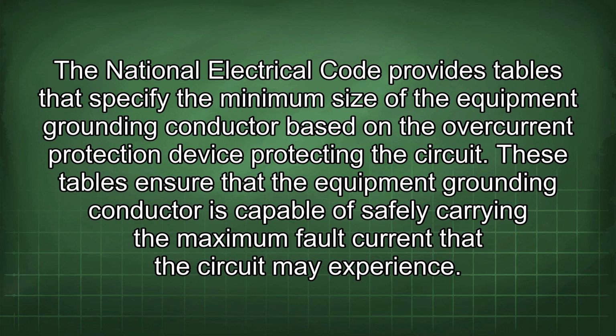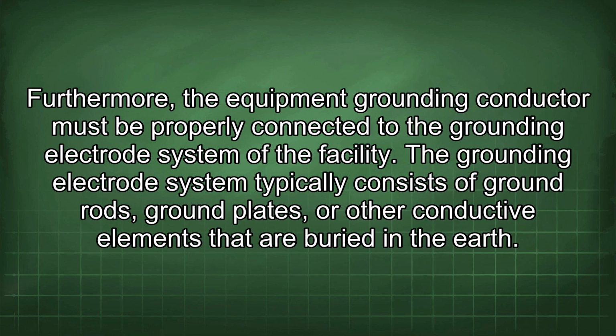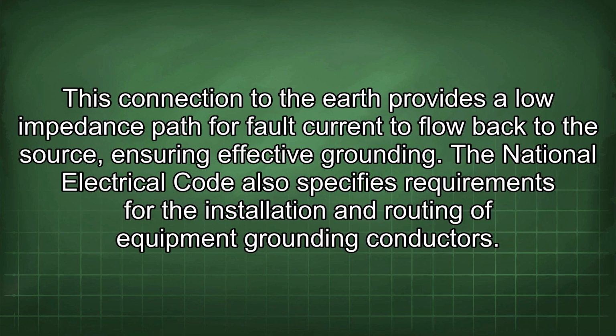These tables ensure that the equipment grounding conductor is capable of safely carrying the maximum fault current that the circuit may experience. Furthermore, the equipment grounding conductor must be properly connected to the grounding electrode system of the facility. The grounding electrode system typically consists of ground rods, ground plates, or other conductive elements that are buried in the earth. This connection to the earth provides a low impedance path for fault current to flow back to the source, ensuring effective grounding. The National Electrical Code also specifies requirements for the installation and routing of equipment grounding conductors.